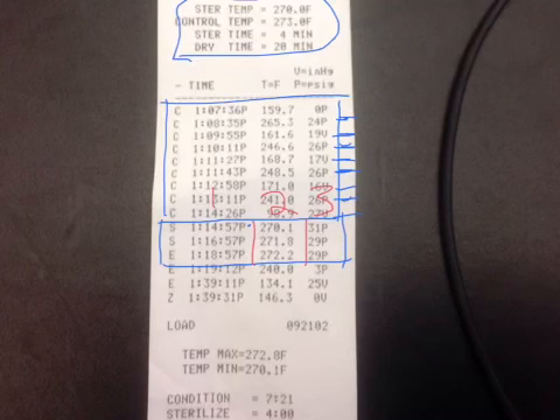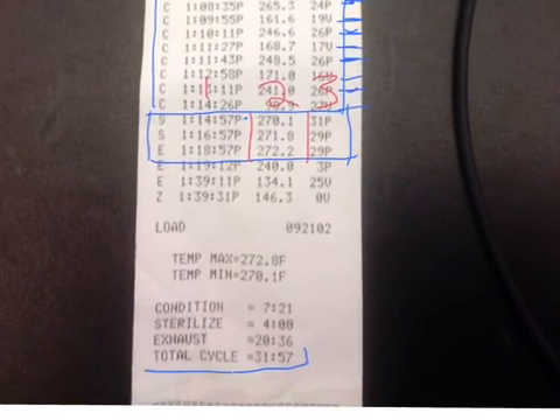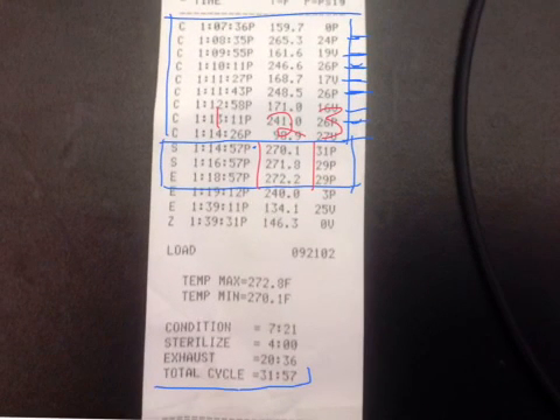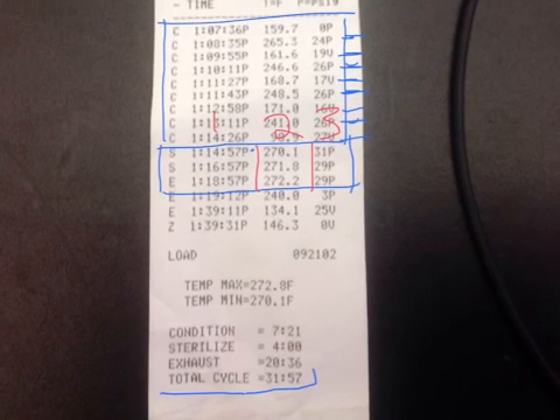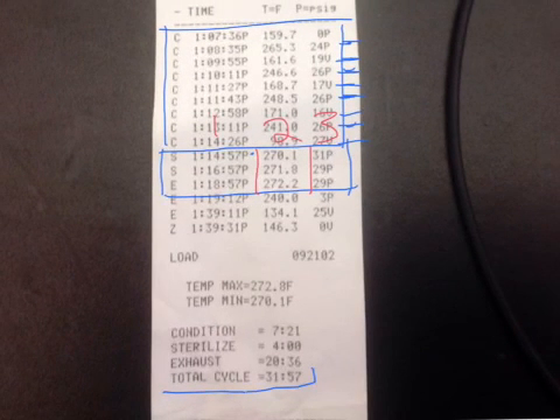We did have the pre-vac before, so we know that the chamber was prepped for the type of item that we're wanting to sterilize. And then we get the 4 minutes sterilization time after the pre-vac conditioning of the chamber. After that, it goes into a 20-minute dry time before pulling a little final vacuum in order to prep the chamber, then to release the pressure altogether and to be ready for unloading. So as I said, it's a pretty extended cycle, but you can see where this type of conditioning of the chamber would be best if you wanted to prep the chamber for something that would be difficult to get steam penetration.